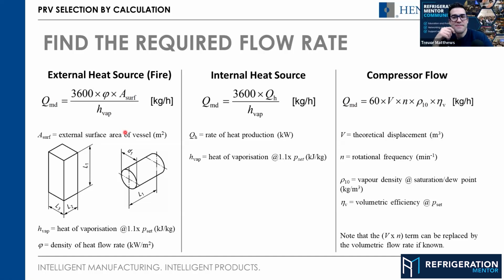So if you have insulation, that is going to affect how quickly the fire heat will be absorbed into the vessel. Yeah, to put that in terms, say you put a lighter on the bottom versus a blowtorch; you're just getting more heat on it quicker. So now with that variation, we're talking about the first requirement, but with the insulation on, because a lot of times it's 1 inch, 1.5 inch, even up to 2 inch insulation on some of these vessels, that will change the sizing and selection of the PRV. It could do. It changes that term at the top. My Greek letter's correct, that's phi. Yep. It is given in the standard as a value of 10 as standard, but it does say you should account for insulation. It'll go up or down depending on type of insulation, level of insulation, etc. And because the top line is multiplied by that, it's going to have quite a big effect. So yeah, it could well change the selection. Yeah, that's cool. It's something I would not have thought of.